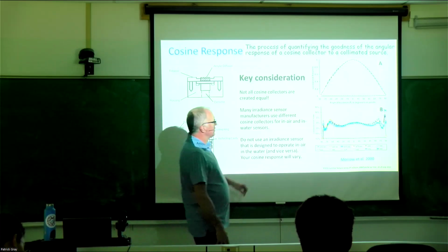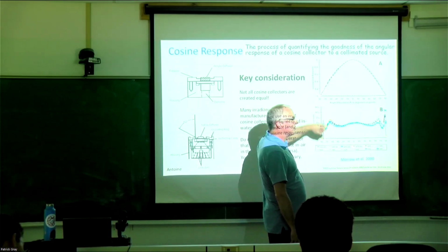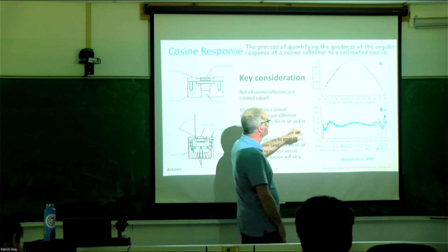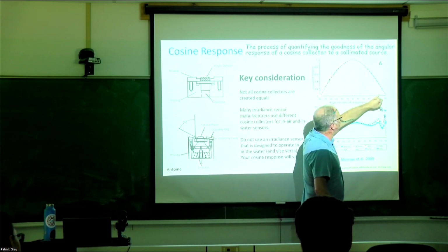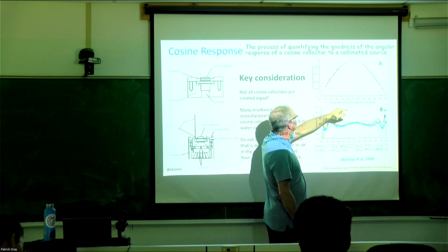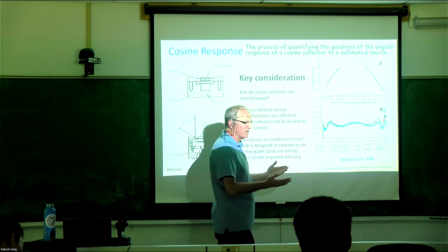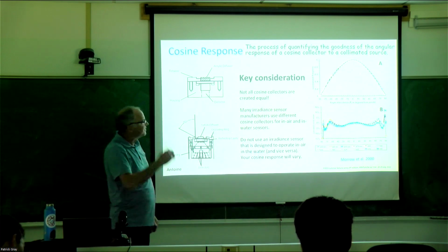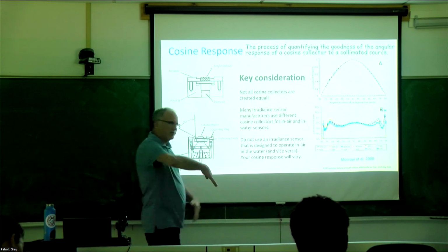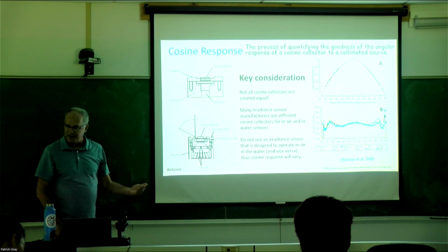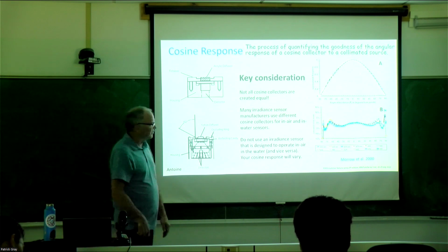So this is basically some graphs trying to show how you would look at the cosine response. Here's the cosine in black, imposed on it. This is the angle of incidence against a normalized response. There's that cosine coming in, its cosine response. And then we make a whole bunch of measurements at very different angles to try to measure what the actual cosine response is in the diffuser.